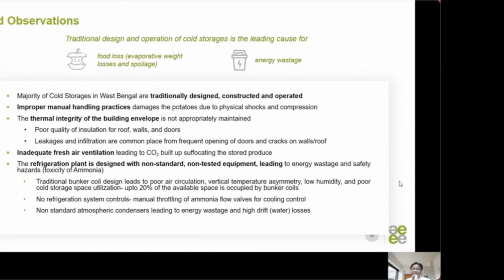Ammonia-based gravity flooded system is the most common refrigeration plant observed in West Bengal. One of the reasons for this selection is low cost, low maintenance, and availability of technicians to maintain the plant. The refrigeration plant is typically run for only 4 to 6 hours per day, leading to suffocation of stored produce and deterioration of its quality.